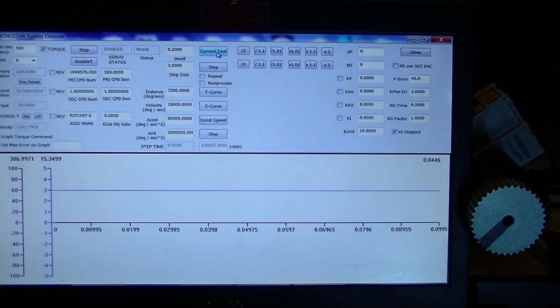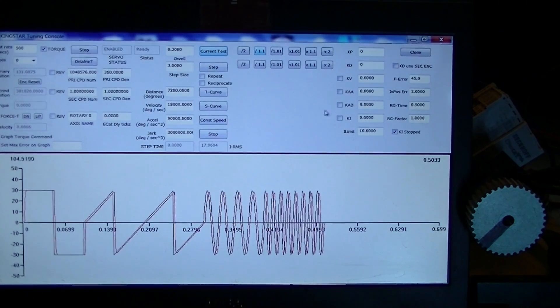The first thing you're going to do is go in here and do a current test. When we hit this current test, you can see that the motor moves. What you're looking at here is simply some commanded torque, 50% forward, minus 50% reverse.